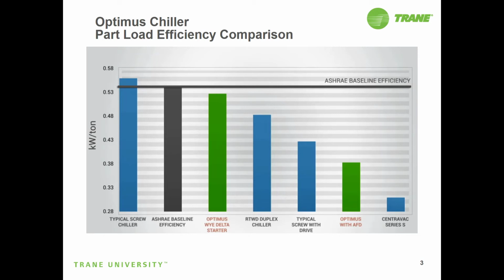Most chillers used for comfort cooling run more part loaded than they do at full load. And process chillers, on the other hand, typically run more full load than part load. So it makes sense that if your chiller was a part load type, the drive would provide energy savings. If your chiller is a full load runner, then the benefits of the drive are reduced.